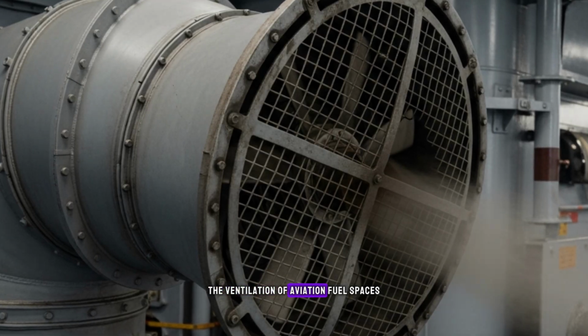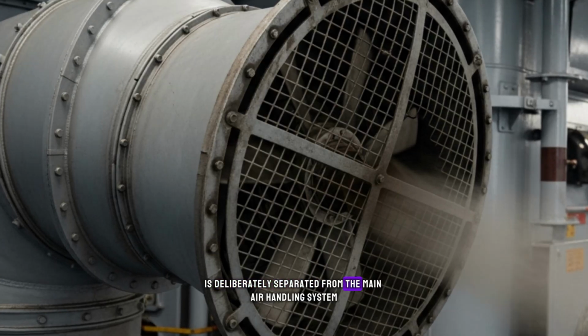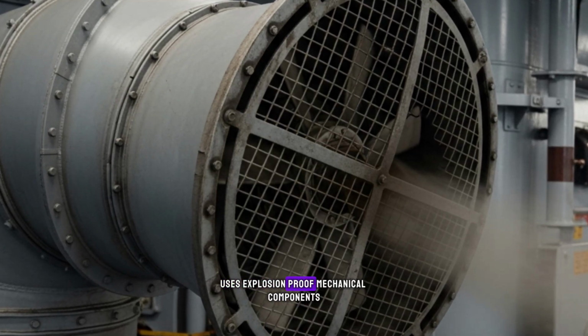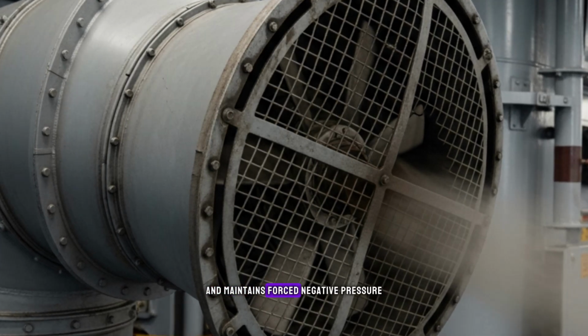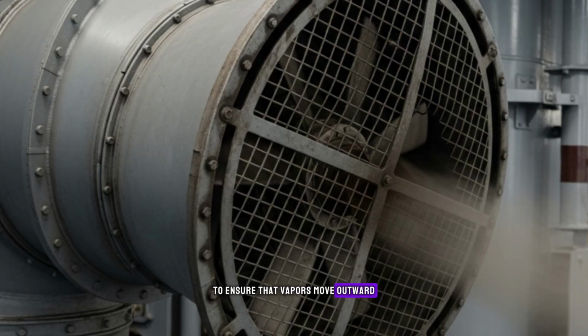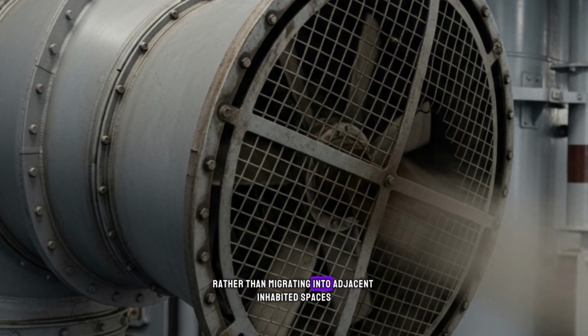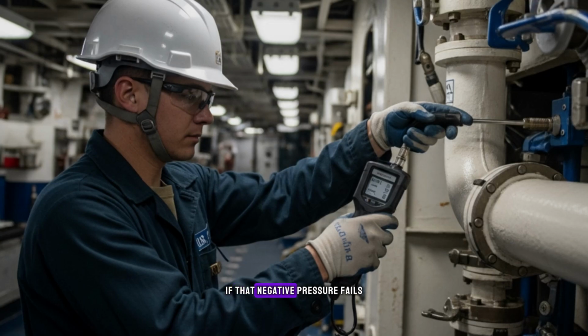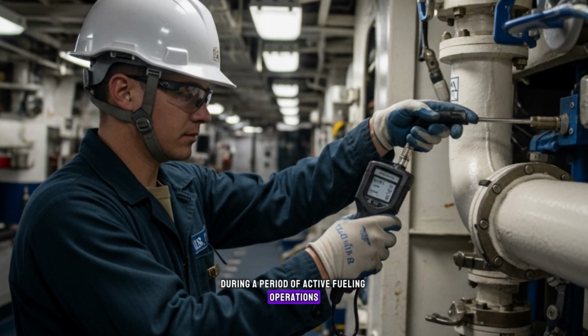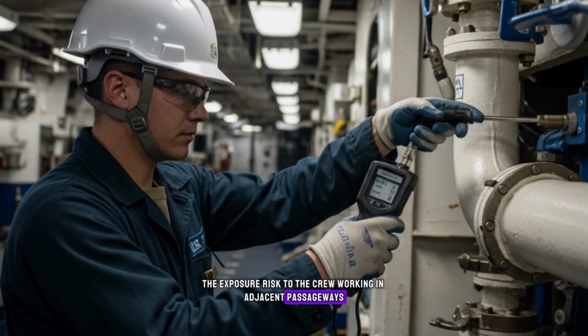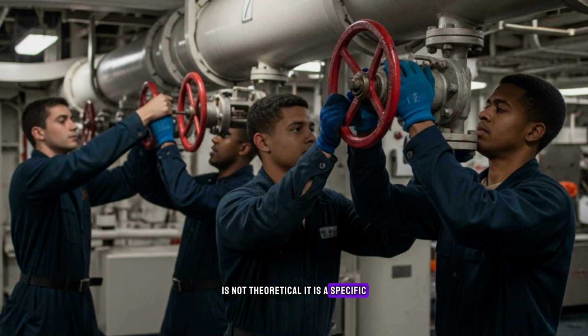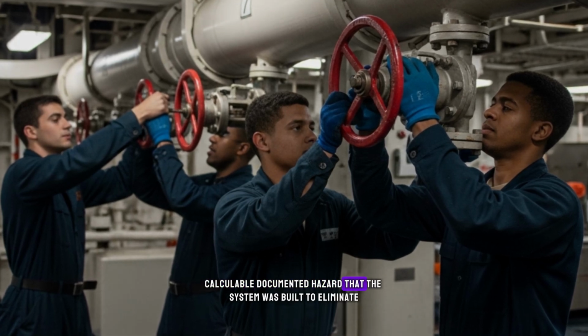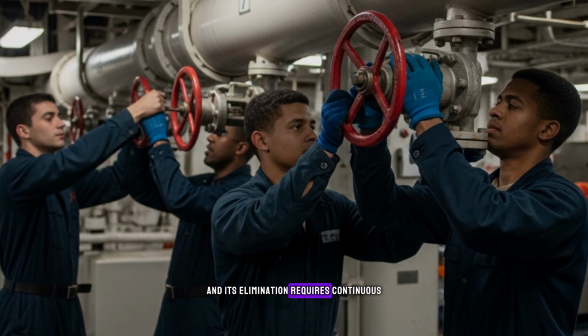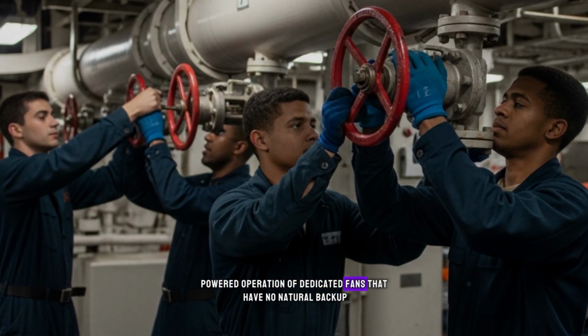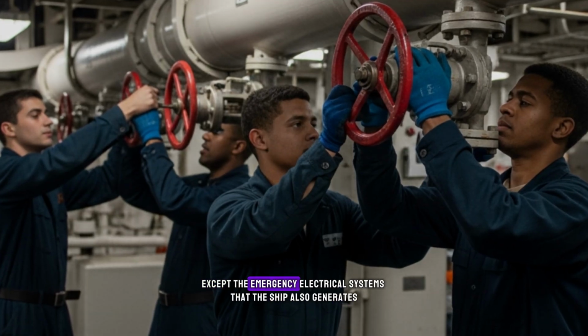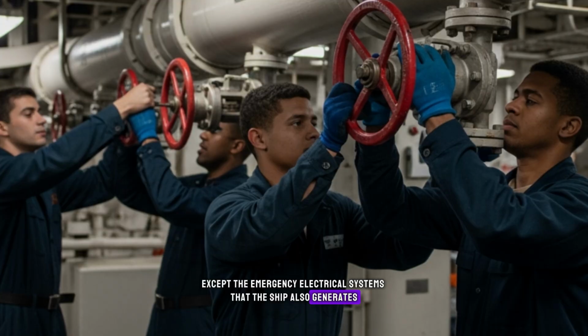The ventilation of aviation fuel spaces is deliberately separated from the main air handling system, uses explosion-proof mechanical components, and maintains forced negative pressure to ensure that vapors move outward toward controlled exhaust points rather than migrating into adjacent inhabited spaces. If that negative pressure fails during a period of active fueling operations, the exposure risk to the crew working in adjacent passageways is not theoretical. It is a specific, calculable, documented hazard that the system was built to eliminate, and its elimination requires continuous powered operation of dedicated fans that have no natural backup except the emergency electrical systems that the ship also generates internally.